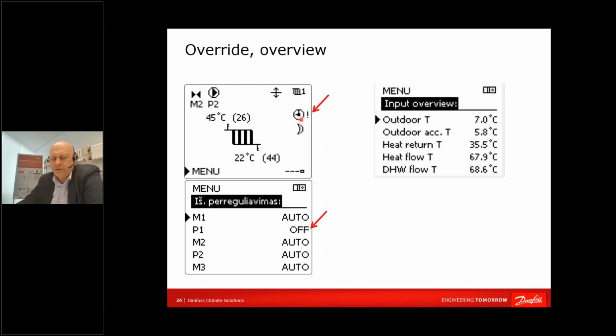One of the things you can also consider when ECL is starting or stopping heating, you can go to menu of input overview, and you can look for the outdoor accumulated temperature. If a real measured temperature is 7 degrees, ECL is calculating outdoor temperature, and it behaves differently. For example, if your heating should be stopped when outdoor temperature is 7 degrees and more, then ECL will stop heating after outdoor temperature will reach 7 plus 0.5, but it will plug in again later on because ECL is evaluating accumulation. So that might be a temperature you can look for.